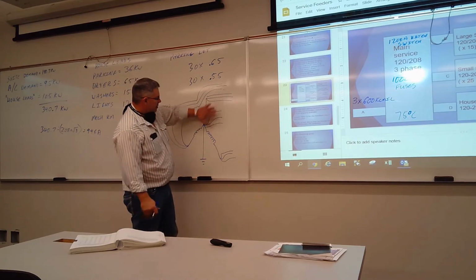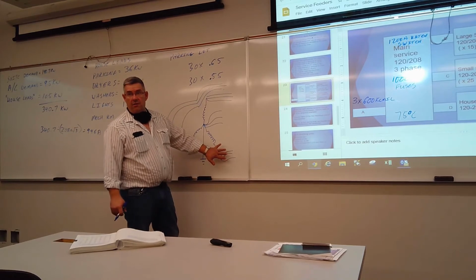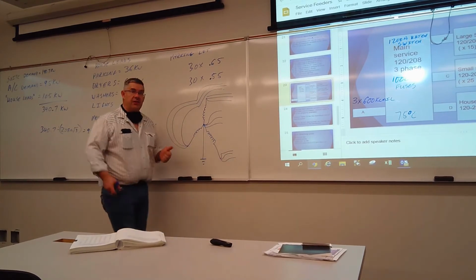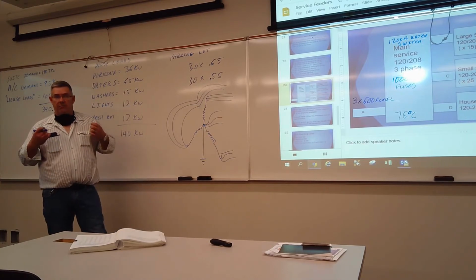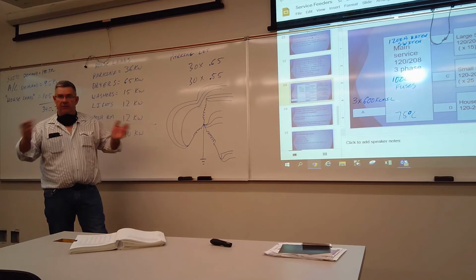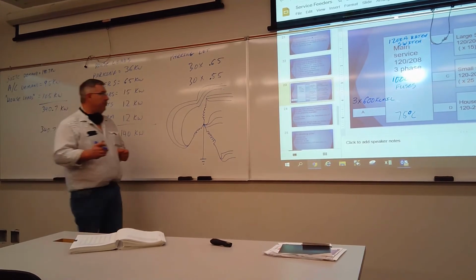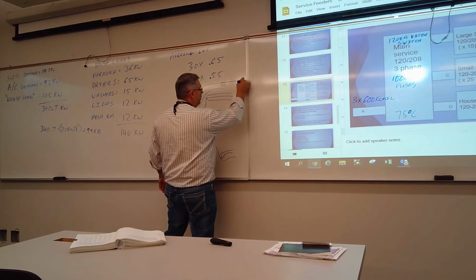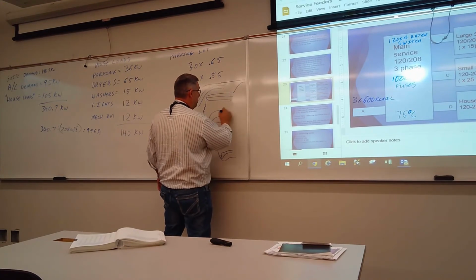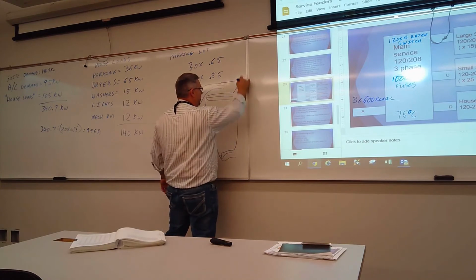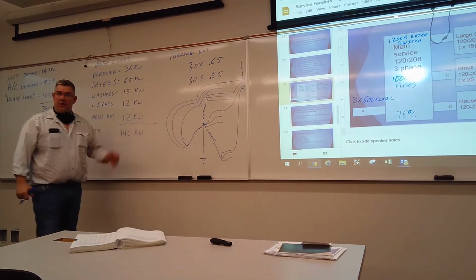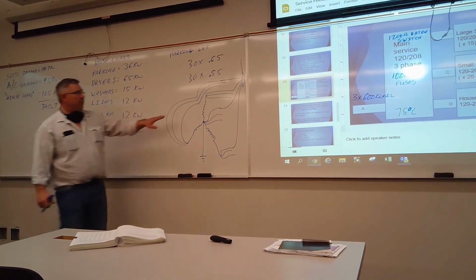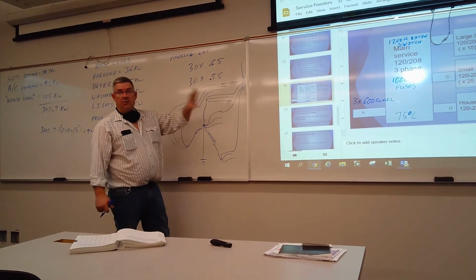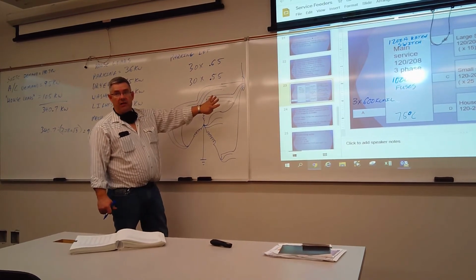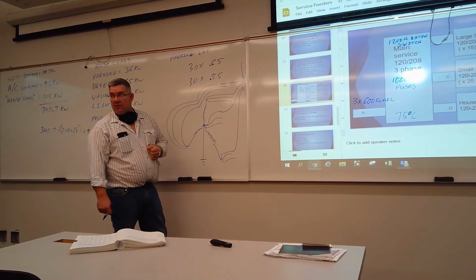Right, so we got 3, 6, 9, 12 conductors, right? Yes. And to make sure that they share the load evenly, and all the magnetic fields work out evenly and everything runs at its optimum, we're gonna put this one, this one, this one, and this one all in one pipe. So you got all 3 phases and a neutral in that pipe, and then we're gonna do the same 2 more times. Okay. So we'll have 3 conduits, each will have 4 conductors in it, and that's how that main service will be built. Does that make sense? Yes.